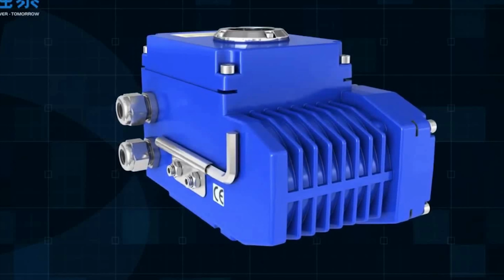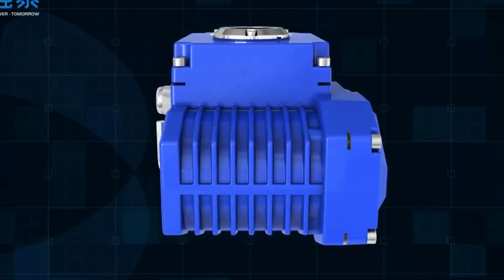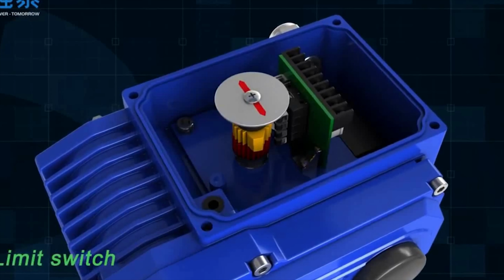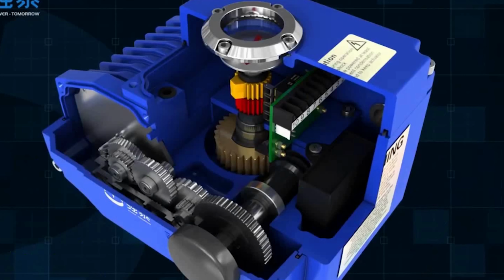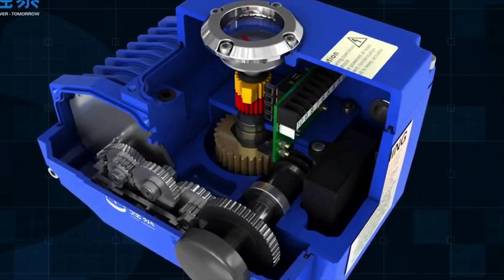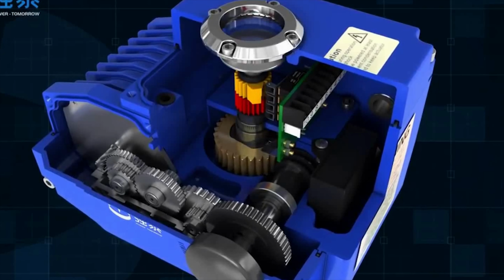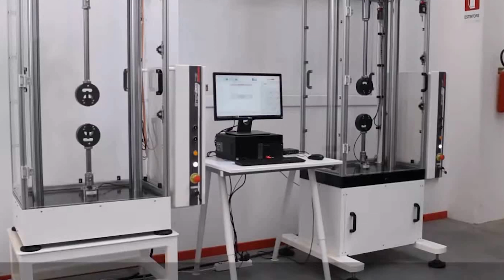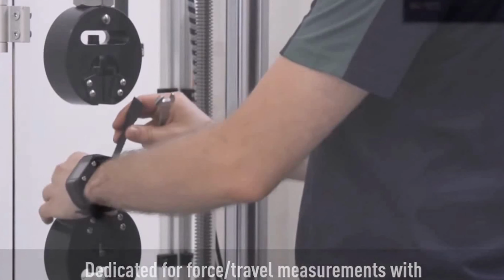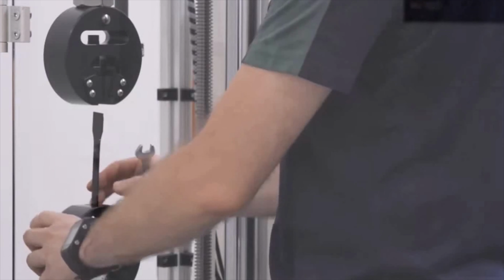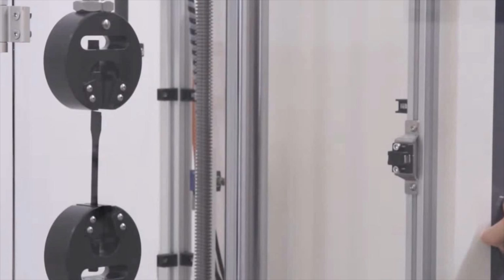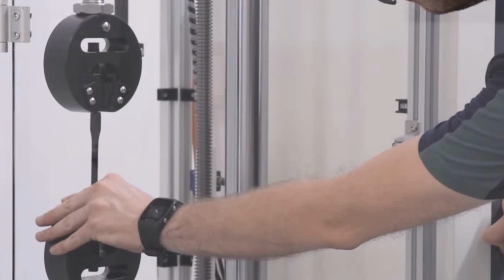Electromechanical actuators. It converts the rotational force of an electric rotary motor into a linear movement to generate the requested linear movement through a mechanism, either a belt or a screw, either a ball or a lead screw, or planetary mechanics. The main advantages of electromechanical actuators are their relatively good level of accuracy with respect to pneumatics, their possible long life cycle, and the little maintenance effort required, might require grease. It is possible to reach relatively high force on the order of 100 kN.